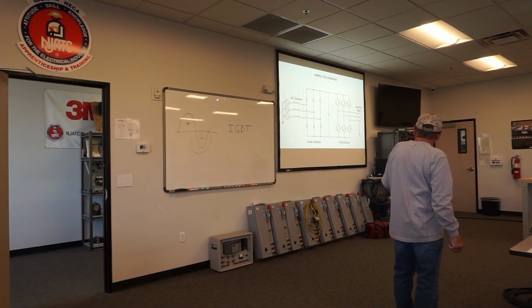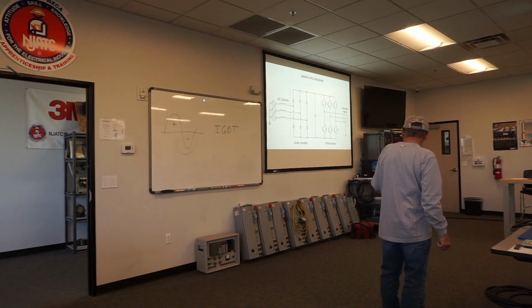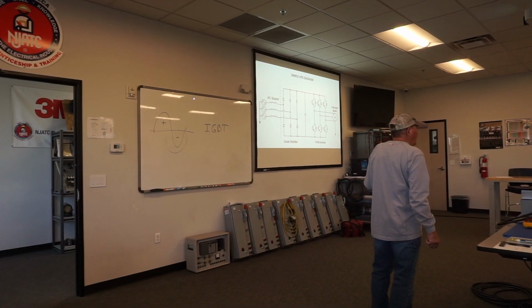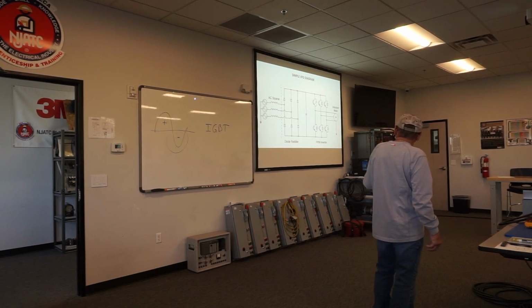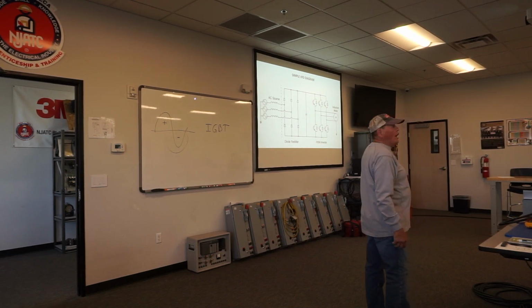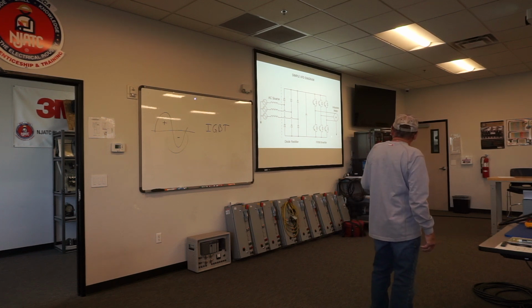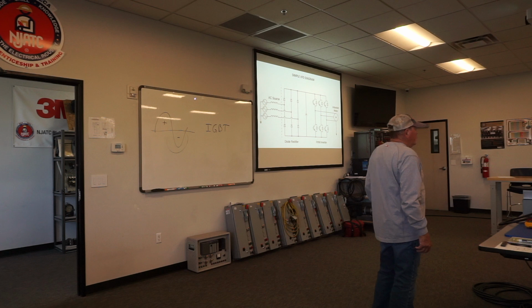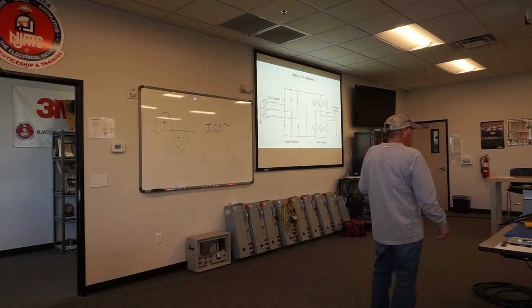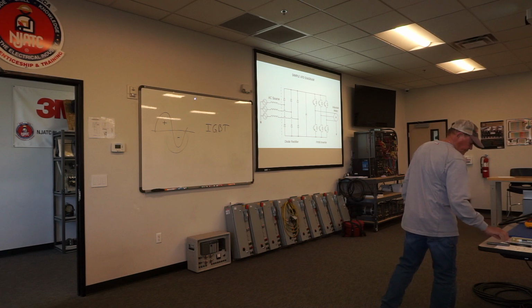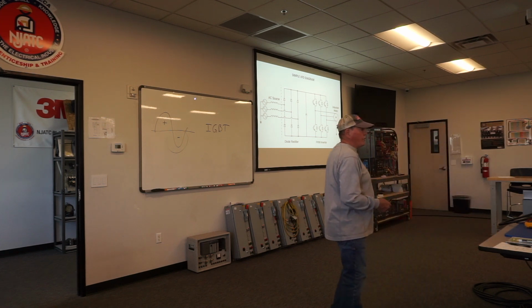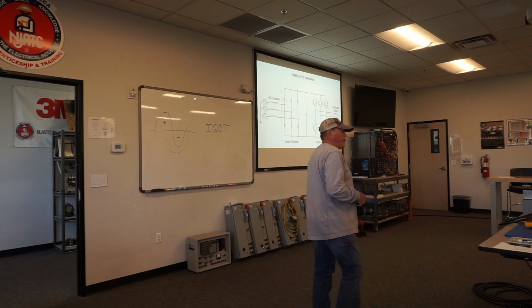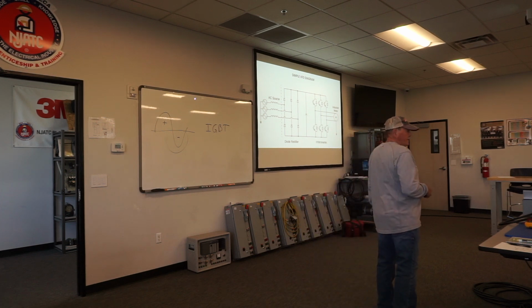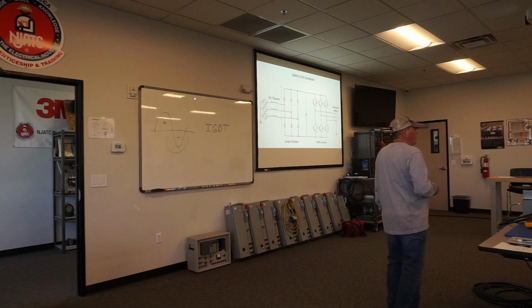Because remember, the output of that motor is going to be somewhere between 4,000 and 10,000 hertz. That means these guys are switching at a very high frequency. Very high frequency. And there's where all the trouble occurs. There's all the dirty power going out that motor, and that dirty power goes both directions. So, the more drives you have on a project, the more dirty power you're going to have. And that's where grounding and bonding becomes so severe.